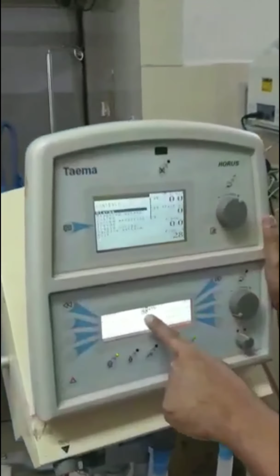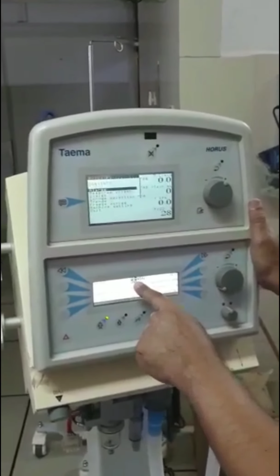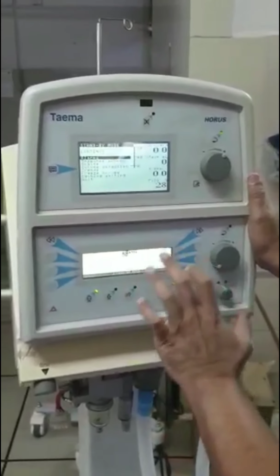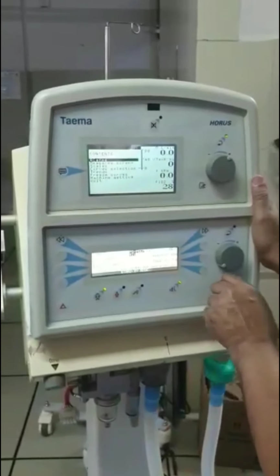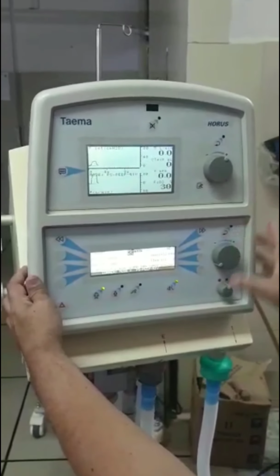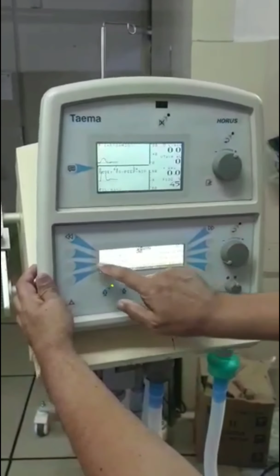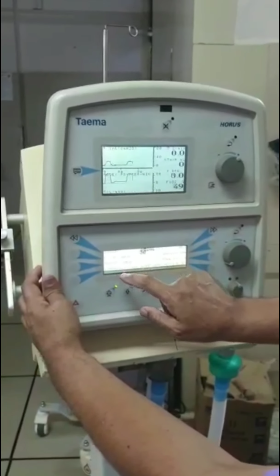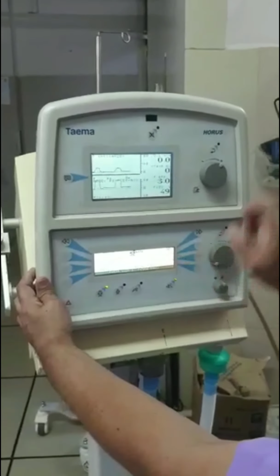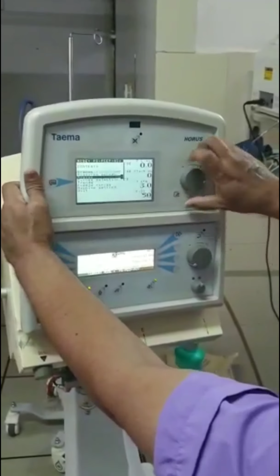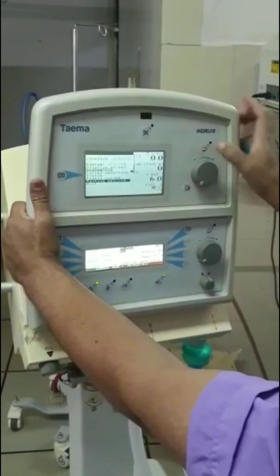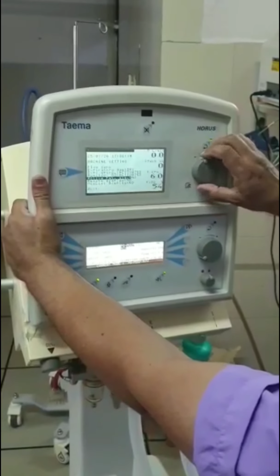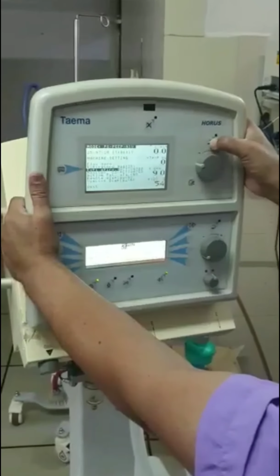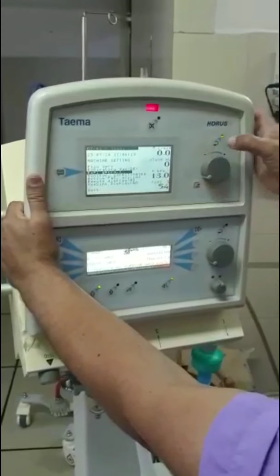Now in the machine we go for PS PEEP NIV. We can go for regular mode also. Non-invasive is preferred. We can use straight away PS PEEP also. PS PEEP NIV, and then switch on the machine, and I've kept a pressure support of 15, PEEP of 5, and respiratory rate at 12. In the machine, if you have option to go to the machine settings and switch off the expiratory spirometer, please do it, so that the frequent alarms in case of minimal leak is avoided.